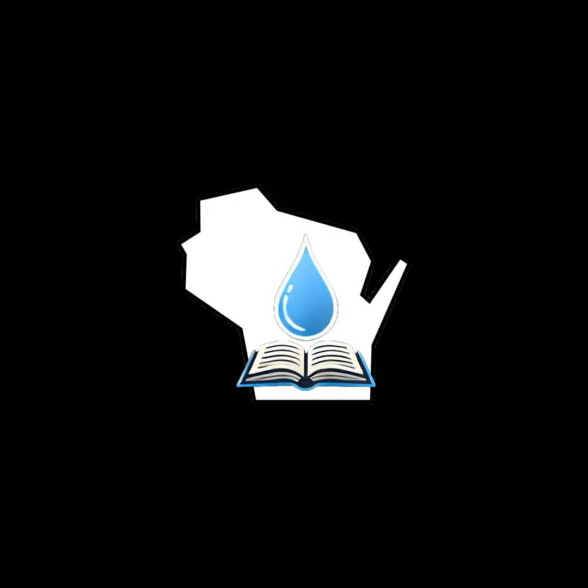Number 6 is combination drain and vent building drain systems. So this is only used in the building drain. Yes, we'll go back to definitions. The building drain means the horizontal piping within or under the fully enclosed portion of a building installed below the lowest fixture or the lowest floor level from which fixtures can drain by gravity to the building sewer.